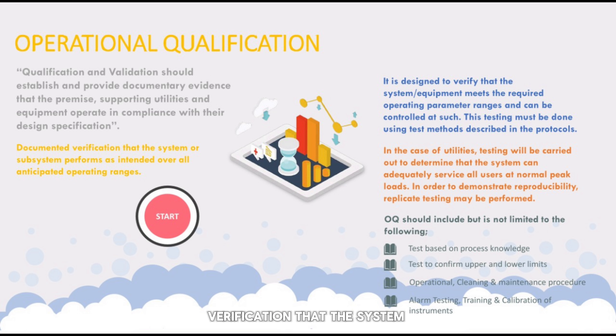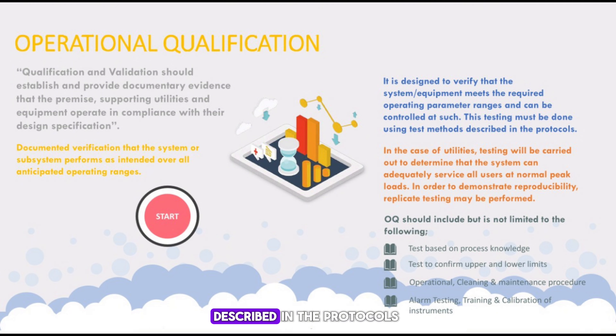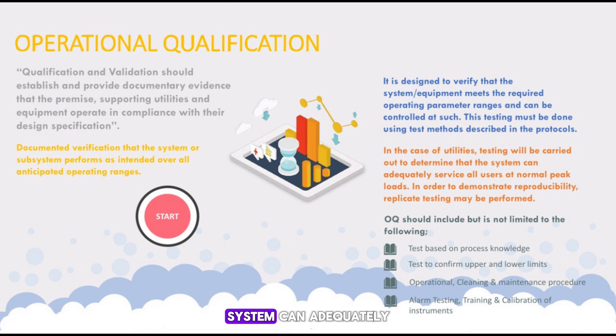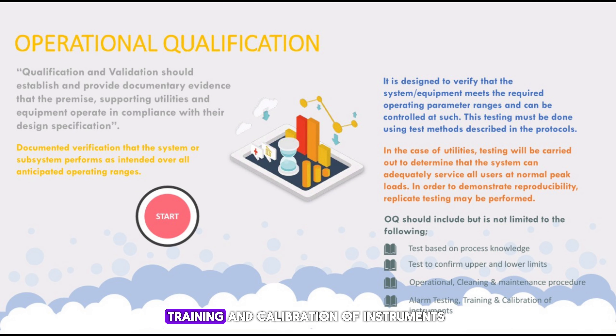What is Operational Qualification? OQ establishes and provides documentary evidence that the premises, supporting utilities and equipment operate in compliance with their design specification. It is documented verification that the system or subsystem performs as intended over all anticipated operating ranges. OQ verifies that the system or equipment meets the required operating parameter ranges. Testing must be done using test methods described in the protocols. For utilities, testing determines the system can adequately service all users at normal peak loads. OQ should include: tests based on process knowledge, tests to confirm upper and lower limits, operational and cleaning and maintenance procedures, and alarm testing, training and calibration of instruments.